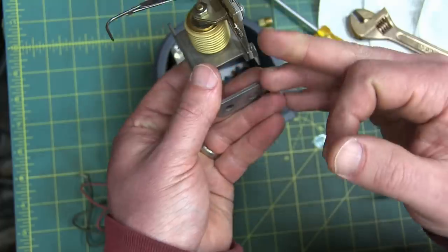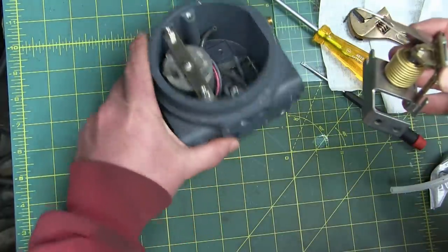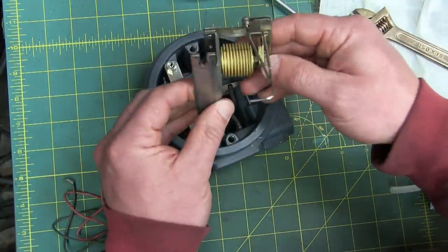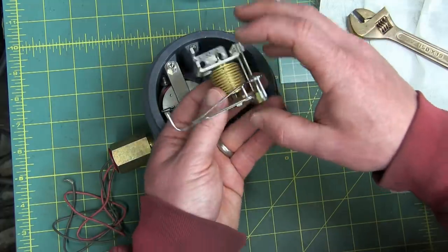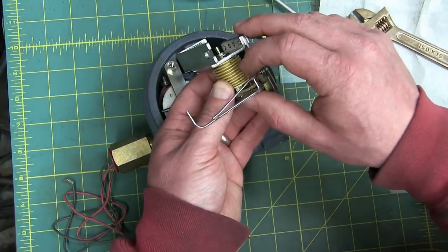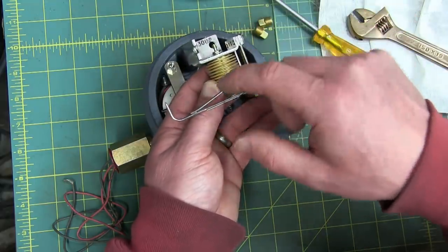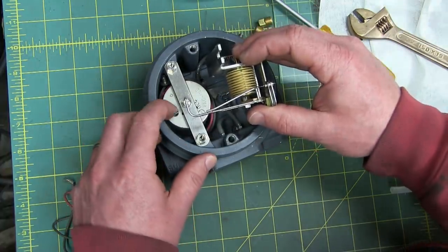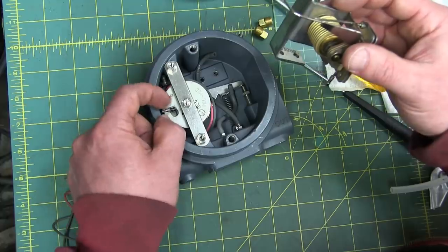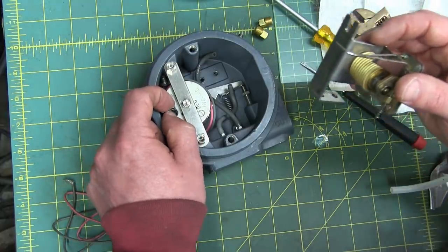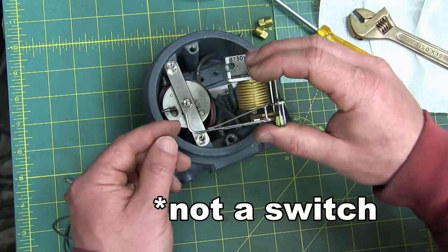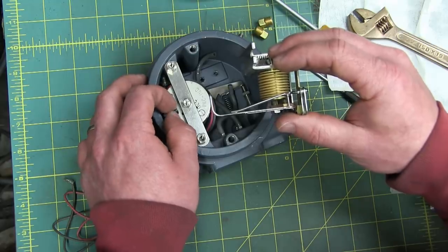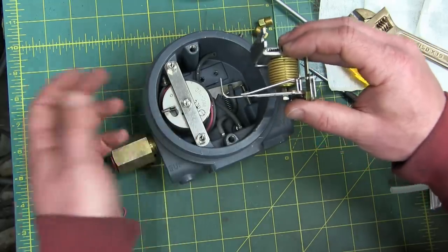But look at this. This itself, this little tube, it's almost like a nozzle. It's a nozzle. Air goes in as well. Now we are missing the bottom platen that gets connected up. But we can sort of infer that this would be the coarse gain or the coarse measurement, and then this would be the fine measurement. We get air blasting onto the rheostat down here. And then there's a contact switch as well. So actually that blowing air might just be for damping, dampening, to take out the oscillations in the system.